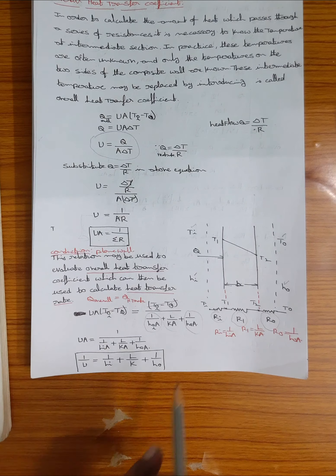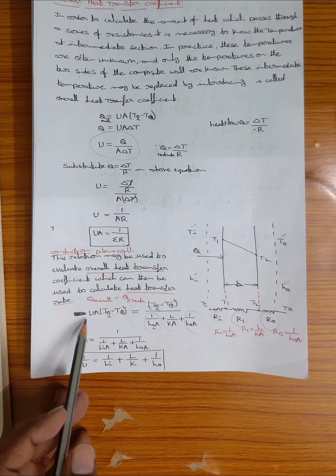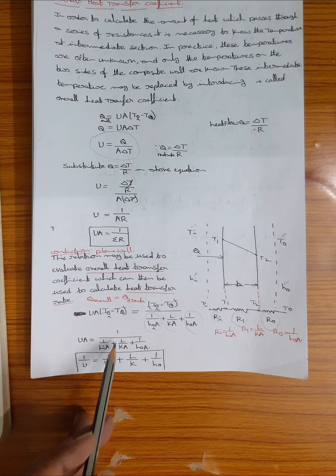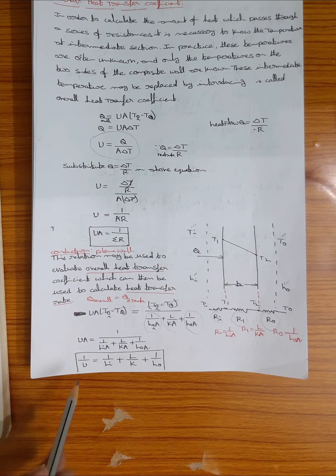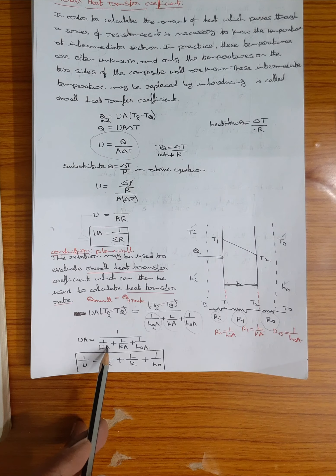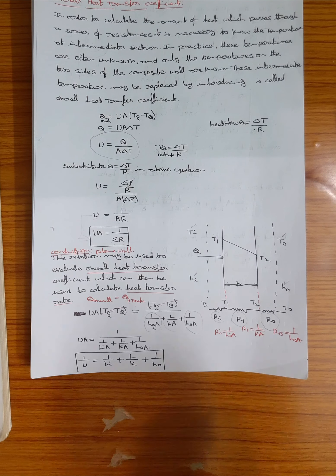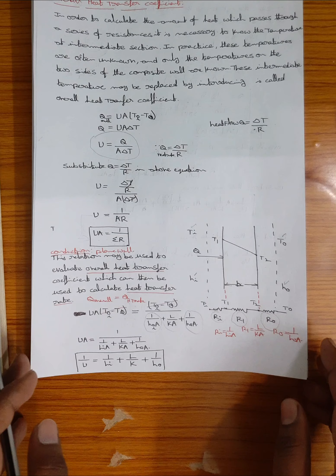After substitution and canceling Ti − T0, we get: UA = 1 / [1/(Hi × A) + L/(Ka) + 1/(H0 × A)]. Dividing both sides by A, the final result for a plane wall is: 1/U = 1/Hi + L/K + 1/H0.